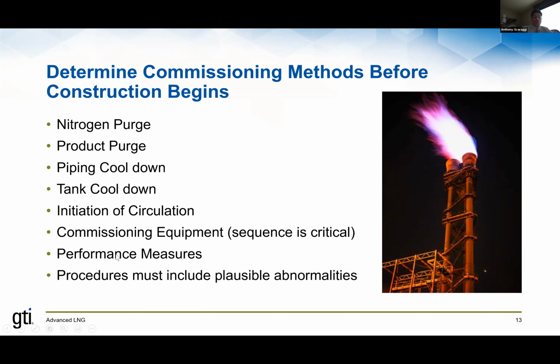When you're considering commissioning, you have to come up with some kind of performance measures to make sure the facility actually operates in the way it was intended to operate, and meets the requirements of the design, right? So you need to have a way to take those performance measurements. You need to have your performance targets, and you need to run your facility to be able to measure those performance measures during commissioning. And things don't always go right. So in your procedures, it's absolutely critical you consider plausible abnormalities that might occur during commissioning, and have plans in place to be able to mitigate those. Okay.